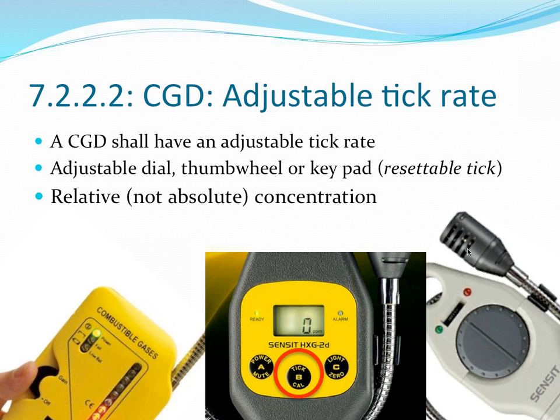So, getting back here, we're talking about relative, not absolute concentrations, but relative concentrations are what's required from the combustible gas detector. You can get a model, such as this one in the center of the screen, that has an absolute or a measurement in it, but that's not required. It's just looking for relative. There was more here, there's less there. You can tell by the tick rate. You can adjust the tick rate to tell whether there's higher and lower concentrations of gas.